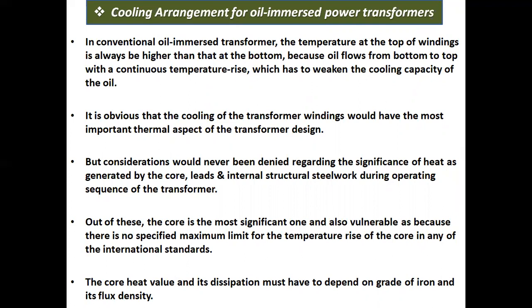But considerations would never be denied regarding the significance of heat generated by the core, leads, and internal structural steelwork during the operating sequence of the transformer. Out of these, the core is the most significant one and also vulnerable, because there is no specified maximum limit for the temperature rise of the core in any of the international standards.